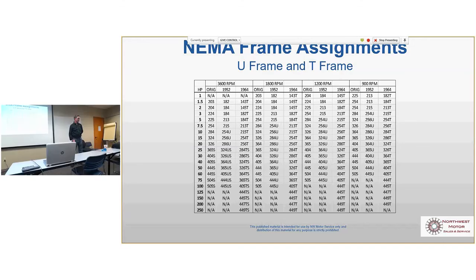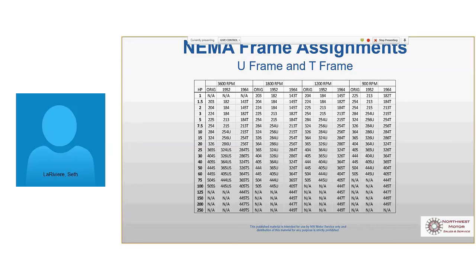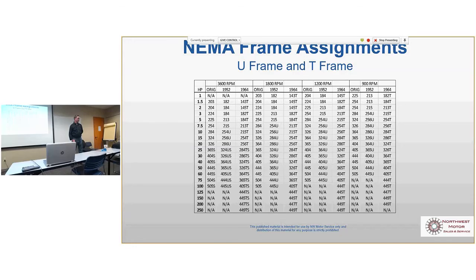But then there are some things that aren't NEMA standard when you're looking at the frame. So the overall length is one that we get into trouble with a lot. You get a replacement motor, the premium efficient designs, which now impact another segment of motors, verticals, crusher duty. There's some other things that are impacted by it. Some of the manufacturers have compensated and made those more efficient to meet those regulations by making them longer, and so we run into that a lot.